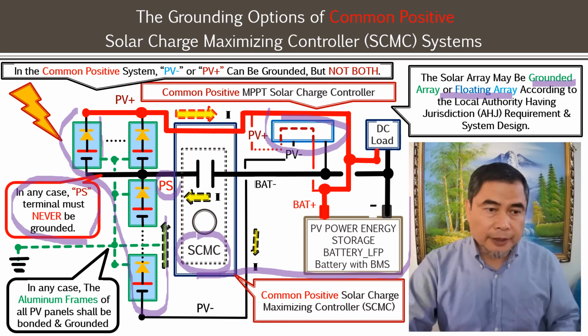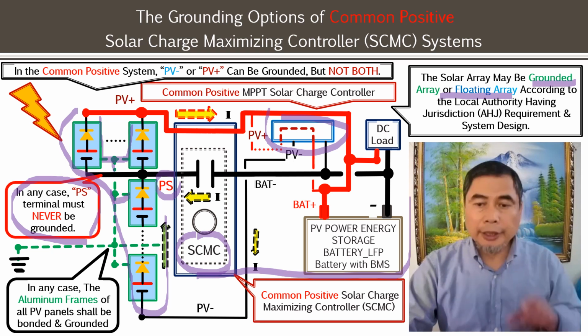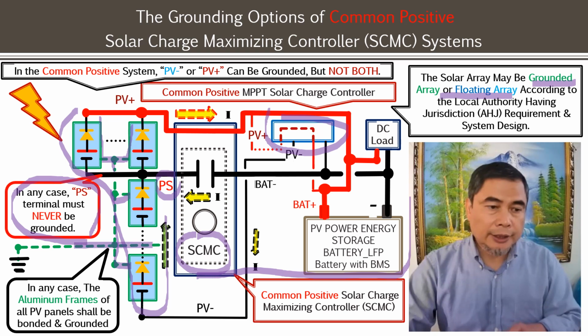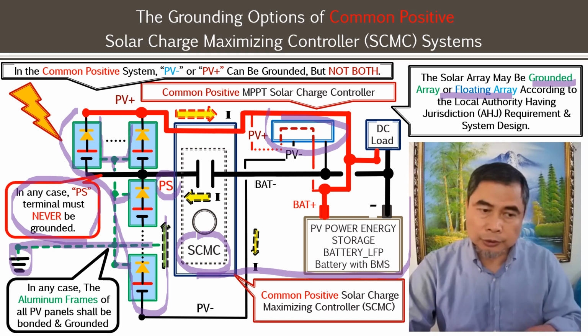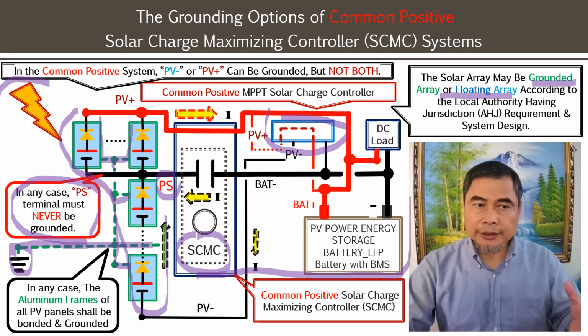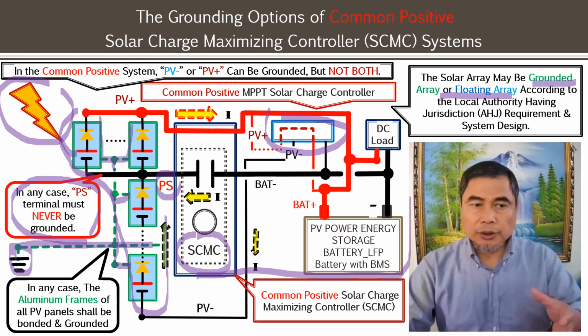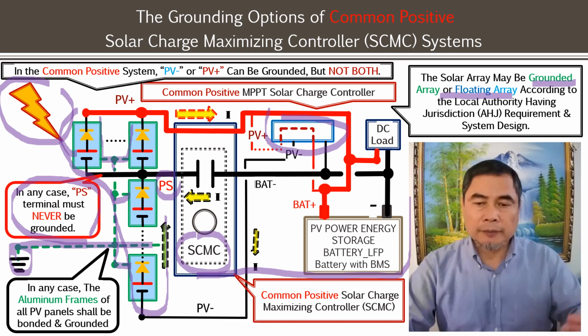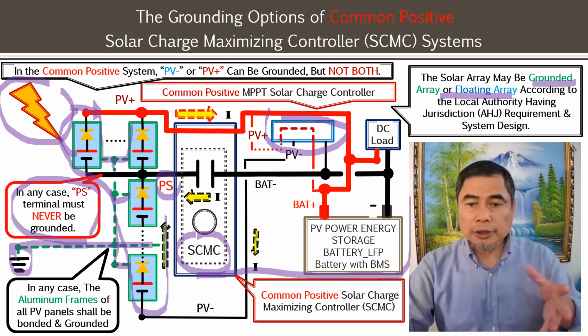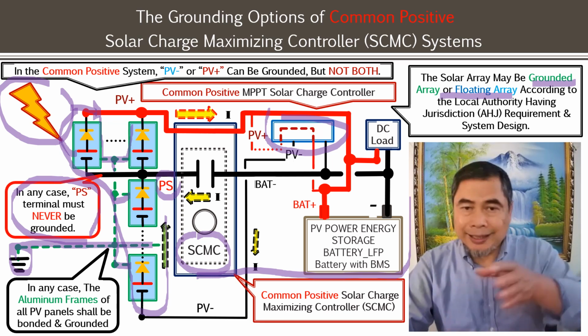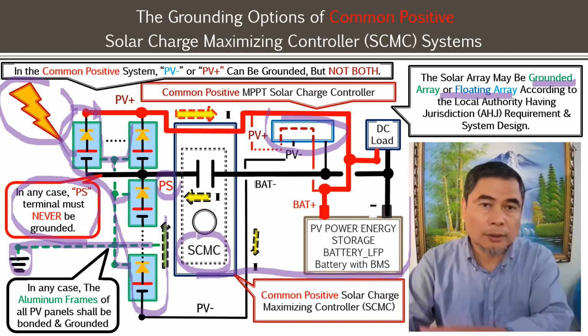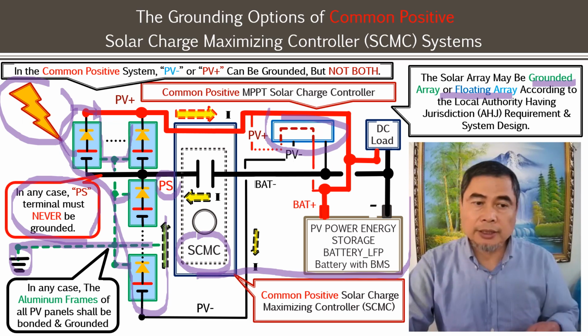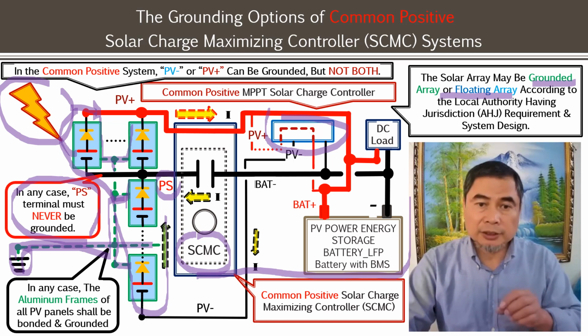However, the aluminum frame, every panel, must be interconnected and connected to the approved ground construction. So when the lightning comes, the high voltage will have somewhere to go. It will not build up voltage that shoots through the solar cables or these solar panels somewhere. The high current will go through the system and cause a lot of damage inside. All other components can be risky without this aluminum frame being connected to the ground, because of lightning. So this is a common positive solar charge controller system design.